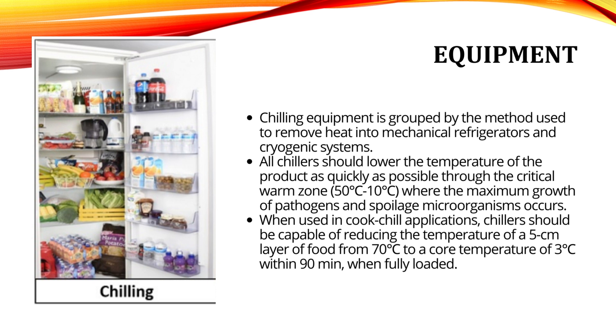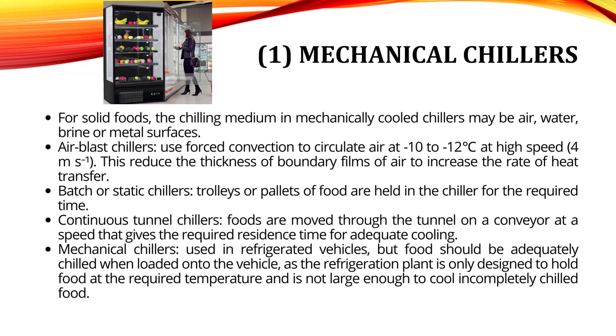When used in cook-chill applications, chillers should be capable of reducing the temperature of a 5 cm layer of food from 70°C to a core temperature of 3°C within 90 minutes when fully loaded. For solid foods, the chilling medium in mechanically cooled chillers may be air, water, brine, or metal surfaces.